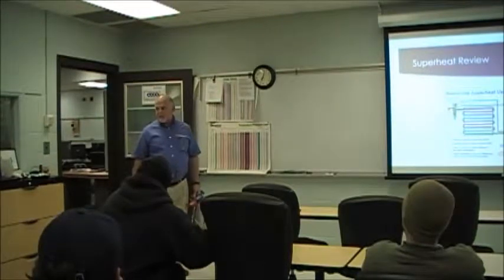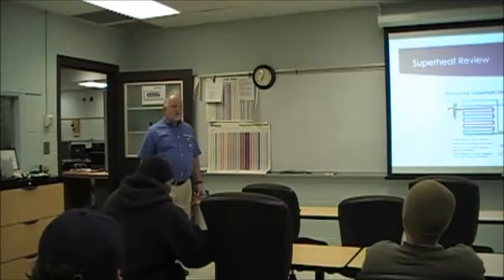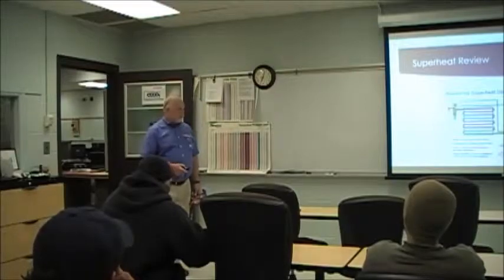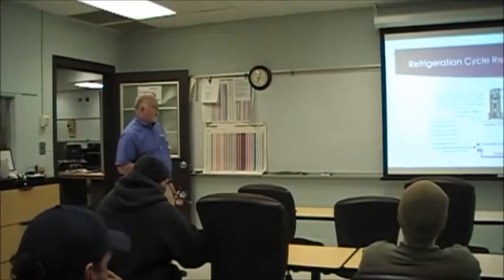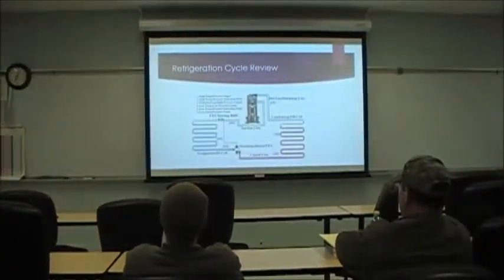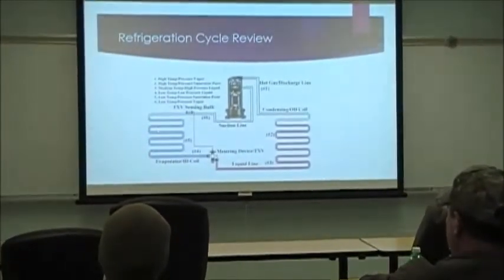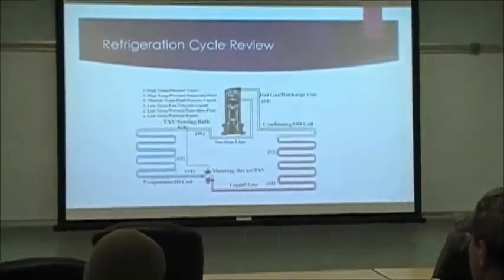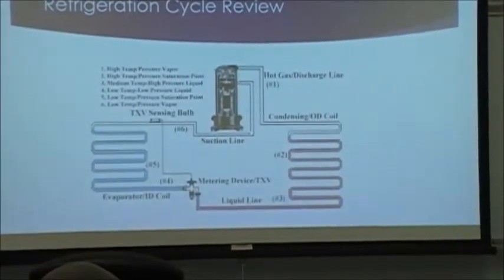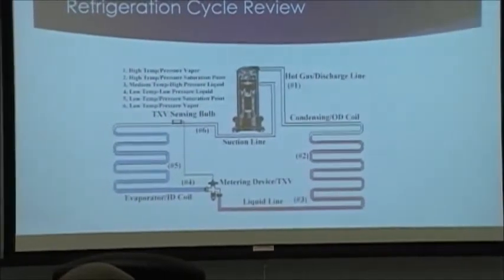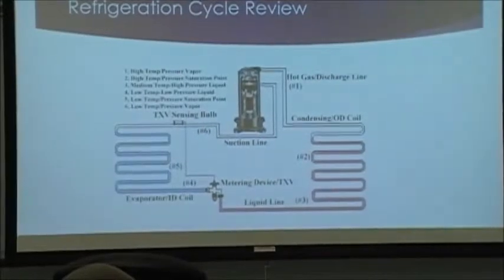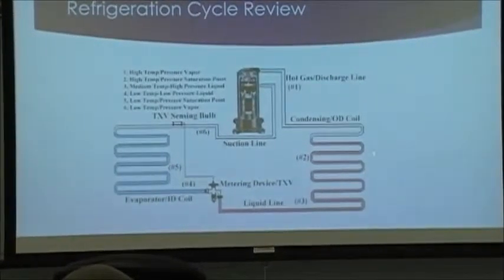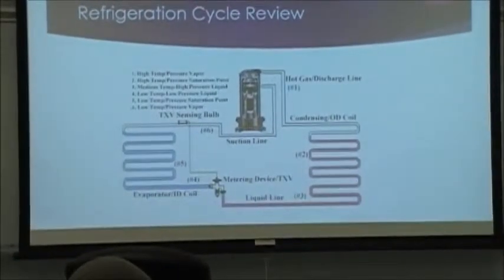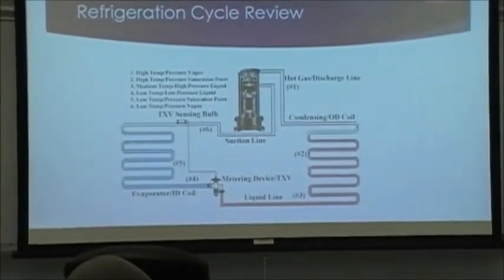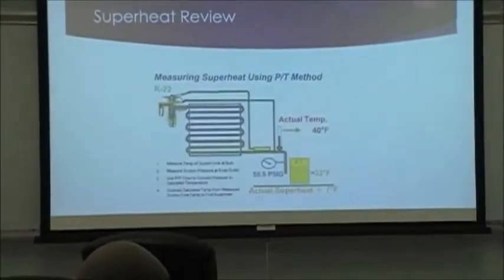That is the saturation temperature. It occurs in two places: the evaporator and the condenser. In the evaporator you'll hear people say we got a 40 degree saturated suction temperature. You'll hear people say I got a 110 degree condensing temperature. That's what those terms mean, the actual temperature. So you take that temperature and convert it to a particular pressure. Saturation occurs at two places in the system.